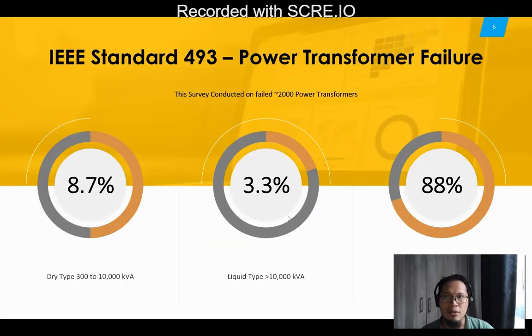According to IEEE Standard 493 for failure, conducted over 2,000 power transformers, 8.7% of dry type varying from 300 to 10,000 kVA failed, whereas liquid type of more than 10,000 kVA failed about 3.3%, and liquid type of 300 to 10,000 kVA failed about 88%. Therefore, it can be seen that liquid type, even though it reduces the overall size and improves reliability, when we don't solve the partial discharge issue, will fail much more often compared to dry type.